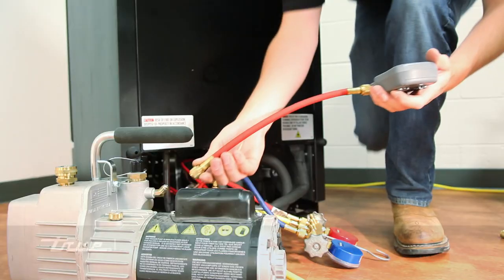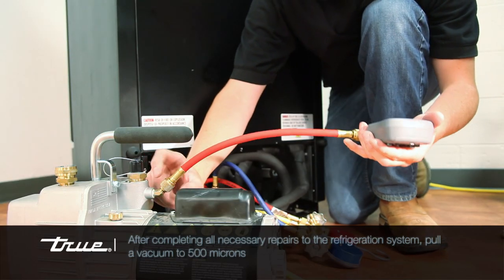After completing all necessary repairs to the refrigeration system, pull a vacuum to a minimum of 500 microns.